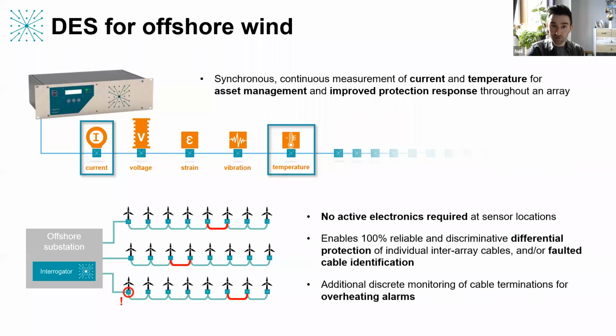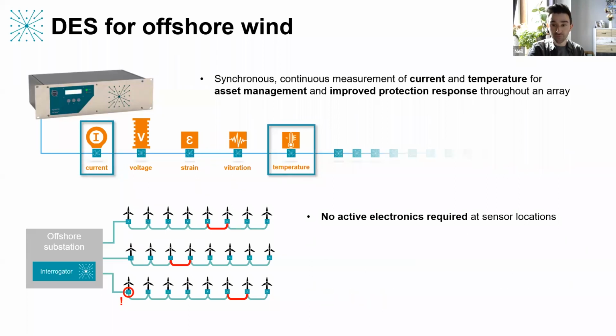If we have discrete temperature monitoring of termination points, then this can be used to monitor trends in temperature and watch out for things like overheating due to ohmic heating of those connectors. And we know from conversations with operators that in some cases, those will be very common points of failure just because that's where manual intervention comes in during the installation. It's also important to note that while a lot of operators will have distributed temperature sensing installed on these systems, typically the sensing fibre that is used for DTS will not measure the termination point. It will come out of the cable and go into the splice box at that point. So it can be very valuable to have, even if DTS is there already, a discrete independent monitor of the temperature of that particular asset.